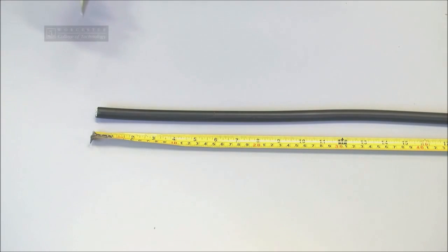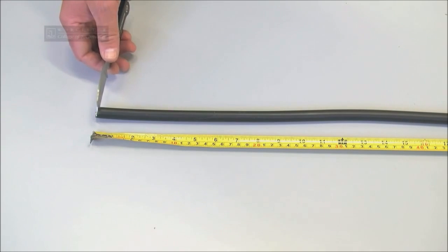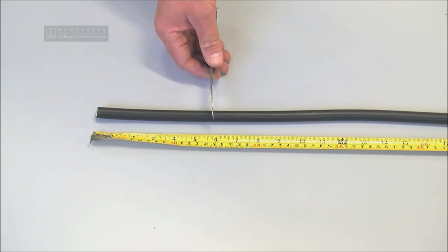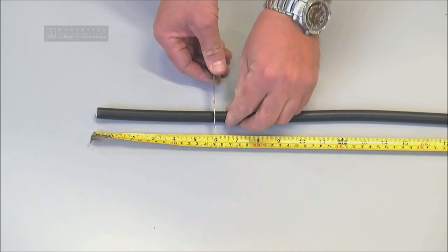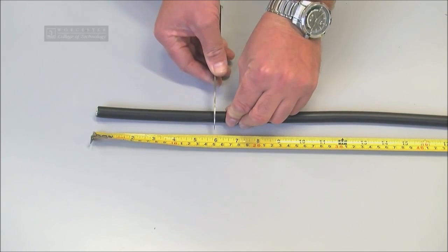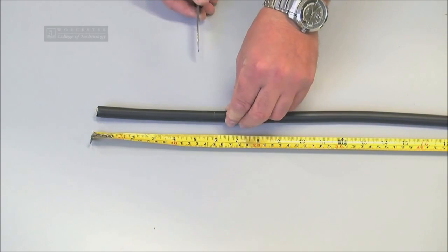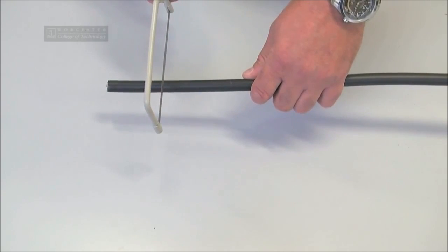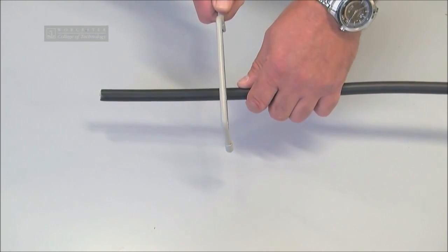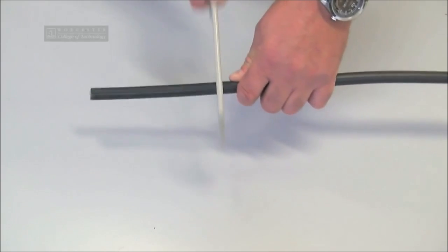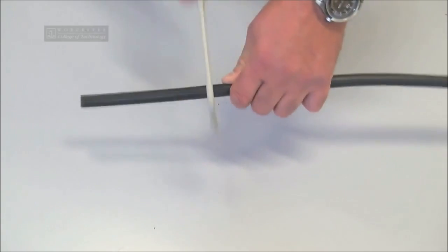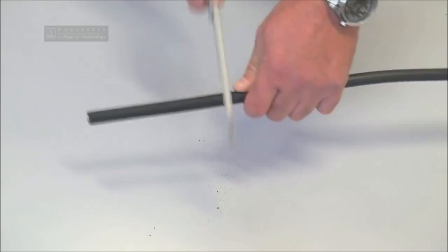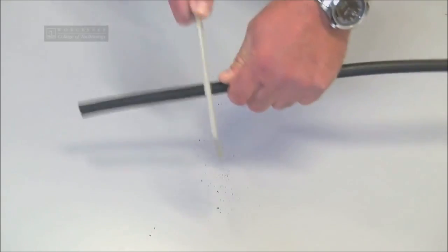First thing we do is we mark off the length of cable required for termination. I've chosen 150mm, so I'm going to score the SWA cable at this point. Next thing we do, we use the junior hacksaw and we cut into the SWA until we go through to the metal braiding and we turn at the same time.